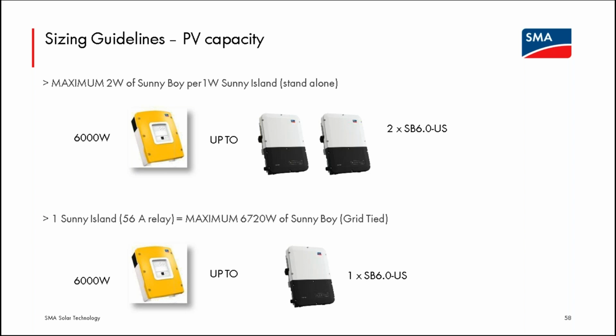The guideline at the bottom of this screen is actually not a guideline. This is a hard and fast rule. The isolation relay in every Sunny Island US is rated to 56 amps. That is going across it from the grid to the protected loads panel, and that current draw is dictated and controlled by the Sunny Island, so it will be respected. But it is also the limit for power coming from the AC1 side, the protected loads panel side, back to the grid. So if PV power is allowed to be backfed through the Sunny Island to the grid, that cannot be more than 56 amps for each Sunny Island. And that's 56 amps at 120 volts or 6,720 watts.